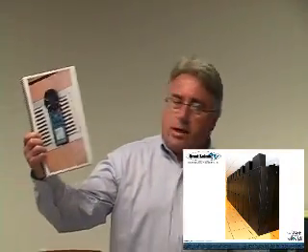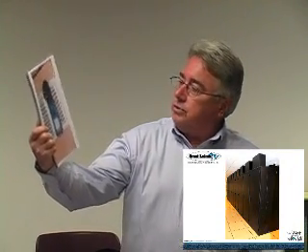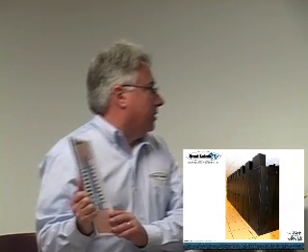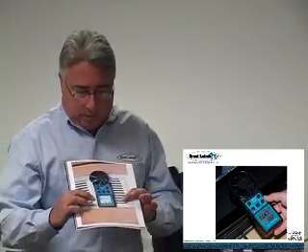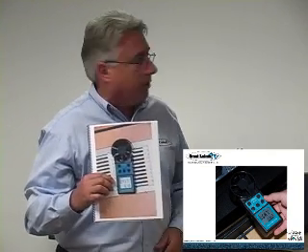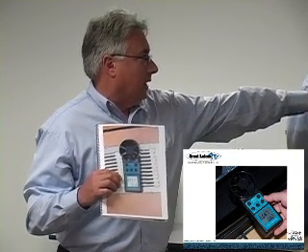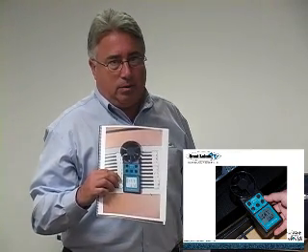I go to the floor tile. That vent, I'll show this to you. Okay, that's in the cab. Well, good. Keep it there. This is the one out of the cab, or out of the floor: 61.8 degrees. Inside the cabin, 60.2.